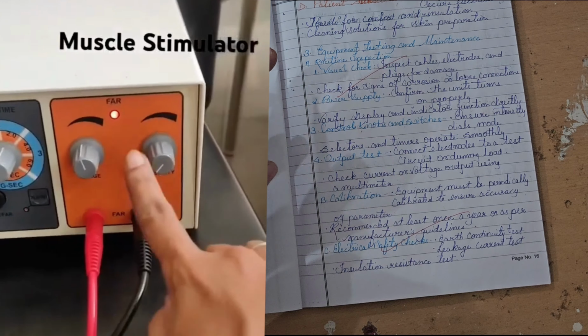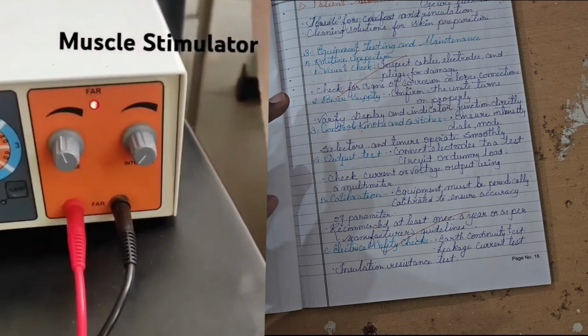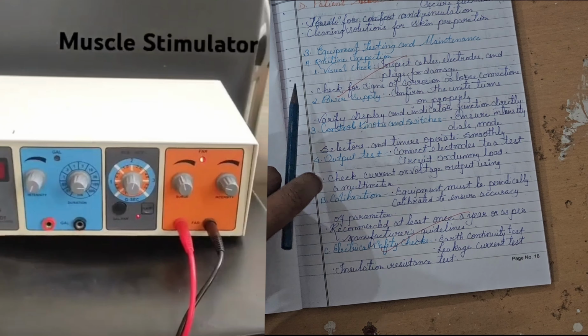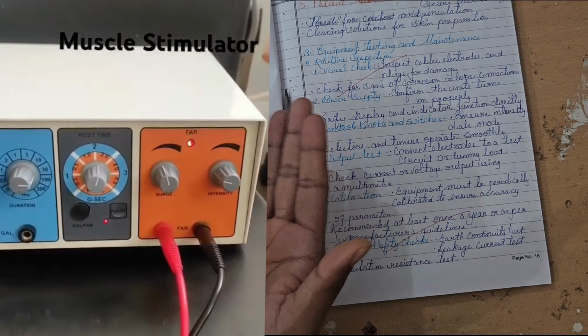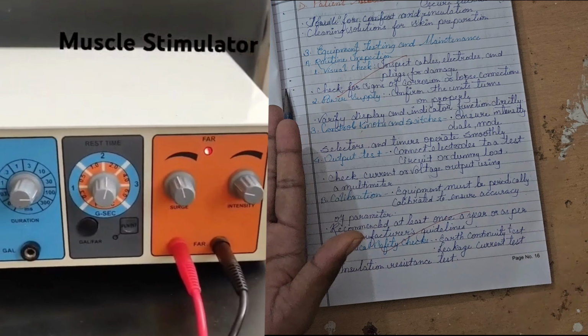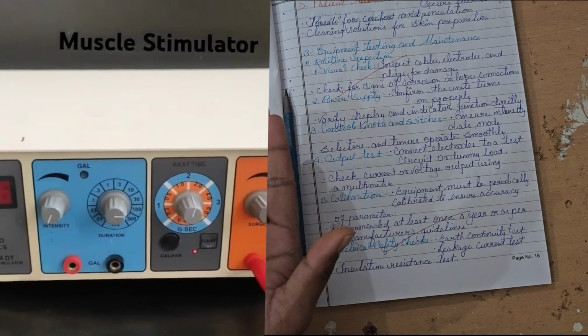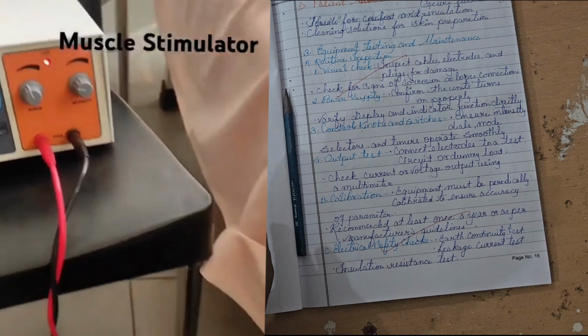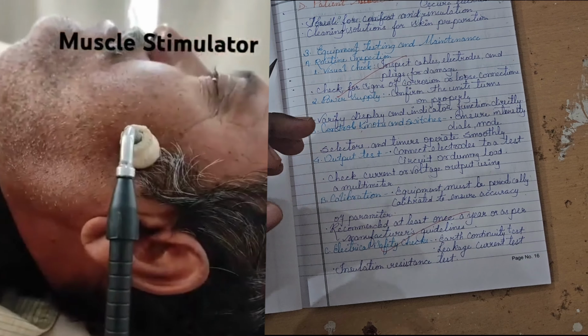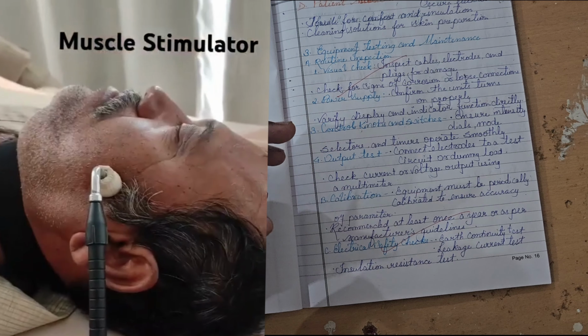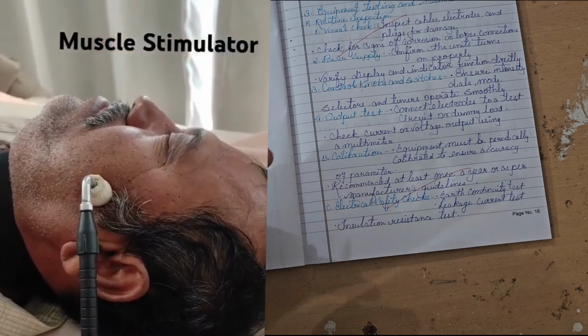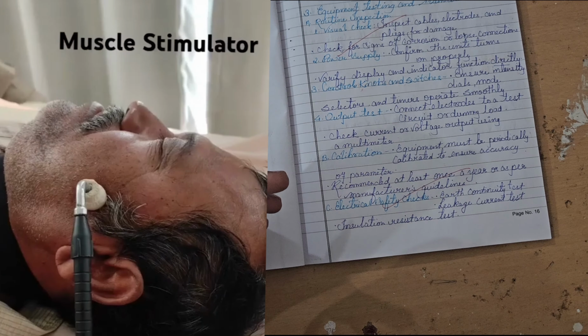Output test: connect the electrodes to the test circuit or dummy load. Check the current or voltage output using the multimeter. You can show it on the screen, the graph. You can apply it first on your screen and check whether the graph is accurate or not. After that you can apply it over the skin of the patient. Calibration: equipment must be periodically calibrated to ensure accuracy of parameters. Recommended at least once a year, as per manufacturer guidelines.